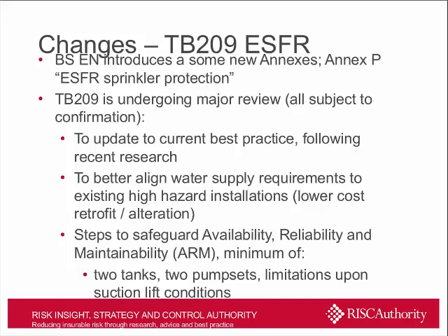TB 209 is subject to a major review at the moment, which is ongoing and should be released in the next couple of months and can just be inserted into the LPC rules. The issues really are that current best practice has moved on a bit. There's been some research undertaken in the last 10 years, which, similar to the point I was just talking about, shows that excessive ceiling clearances are problematic for ESFR systems as well in certain circumstances.